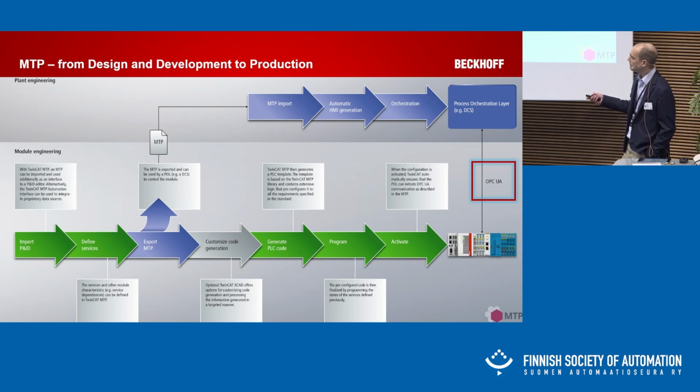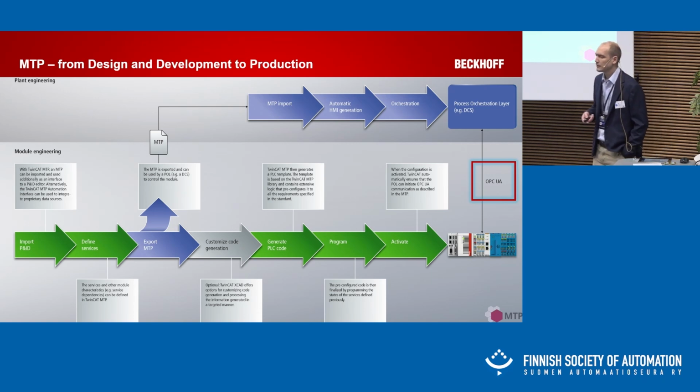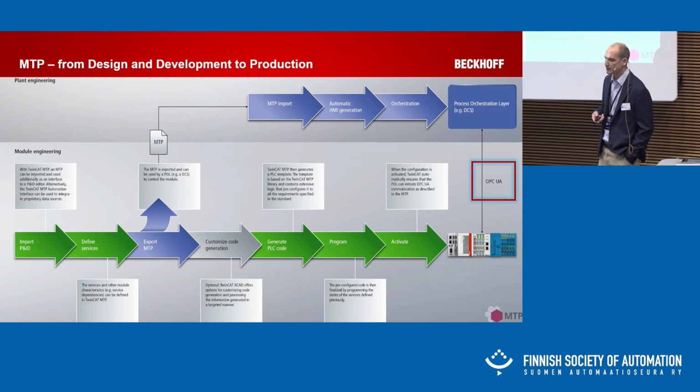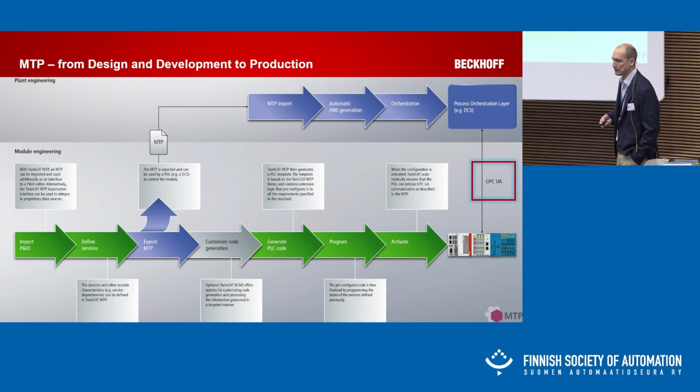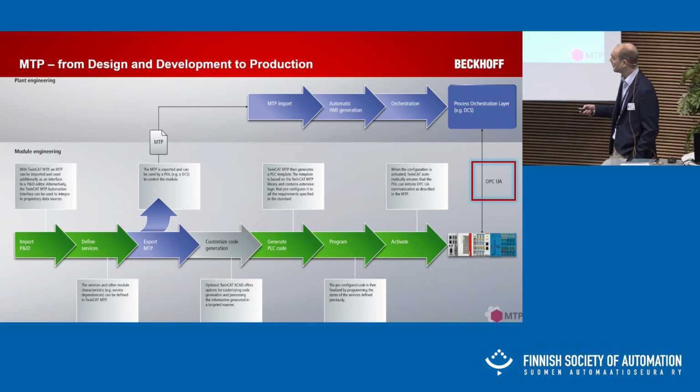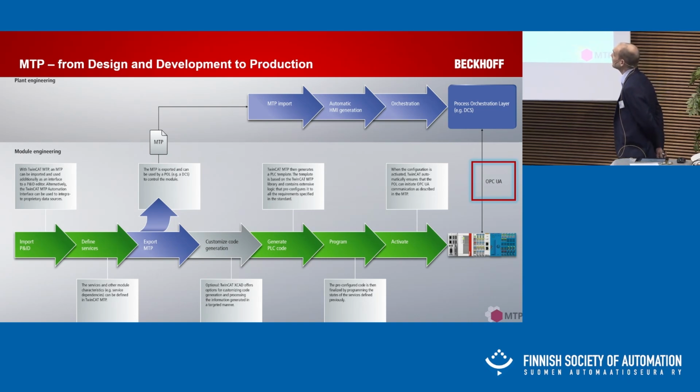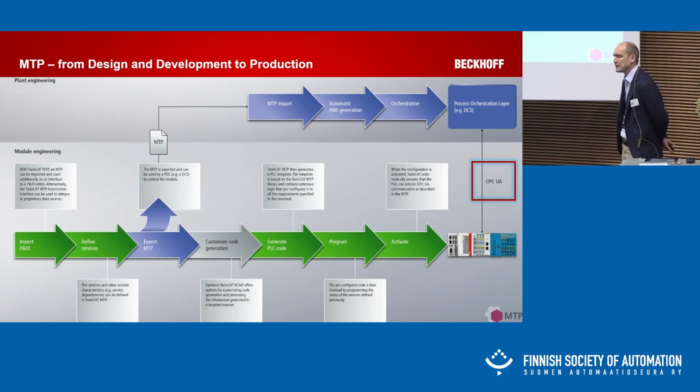At this point of the design process, we can already write this MTP description file fully and export it to the higher level where the plant engineering is done. So we import the MTP file there, and part of this MTP file also includes the description of the HMI components, so they can be automatically generated.